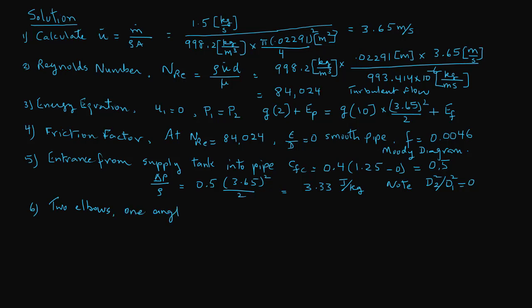The two elbows and the angle valve also contribute frictional energy. That is: ΔP/ρ = (2 × 1.5 + 2) × (3.65² / 2), where 1.5 is the loss coefficient for each elbow and 2 is the coefficient for the angle valve, both obtained from standard tables. This equals 33.31 joules per kilogram.